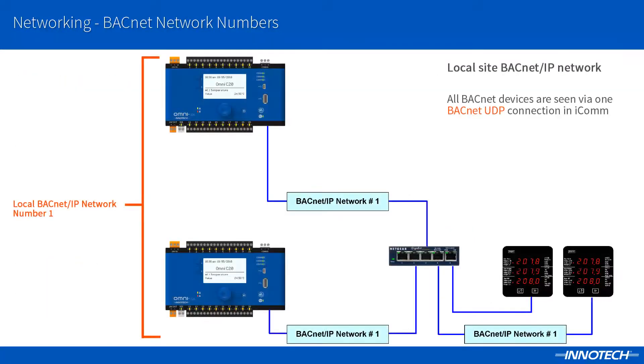On this local site, we have two Omni controllers and two BACnet over IP power meters connected. As this is using a local network for communications, there is only one BACnet network required. Its network number is set to the default of 1. All BACnet devices will be discovered via one BACnet UDP connection in iComm.